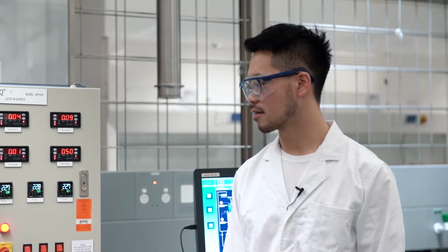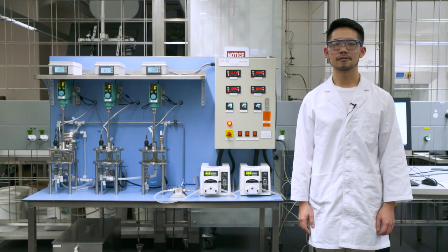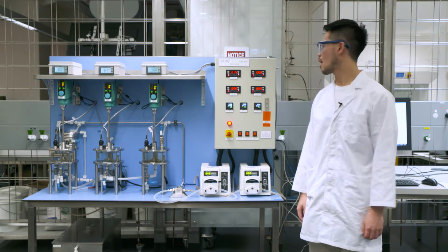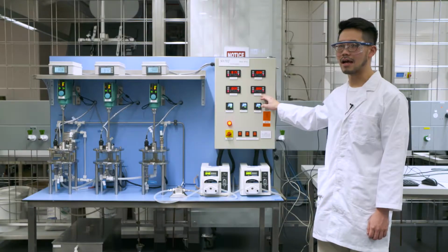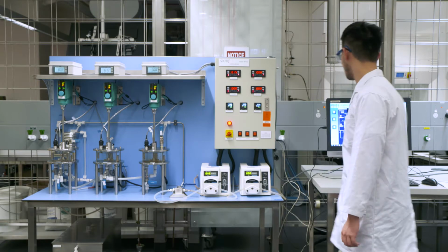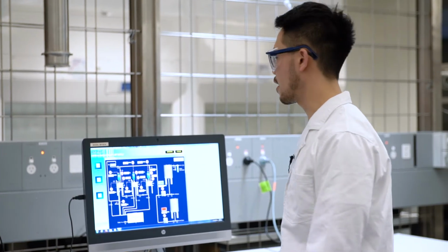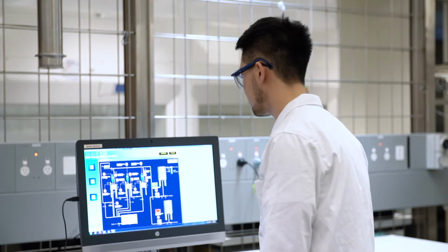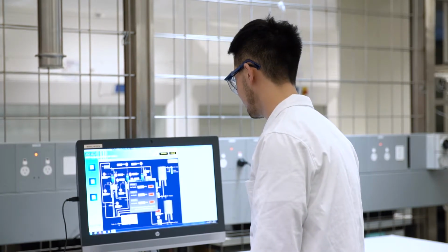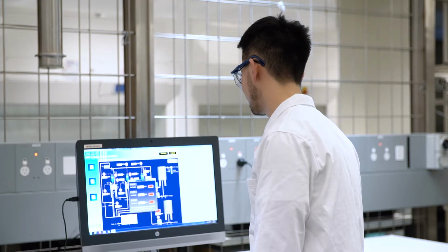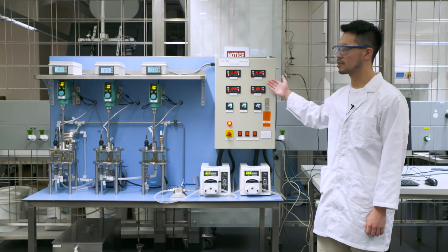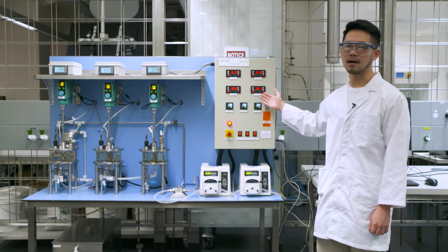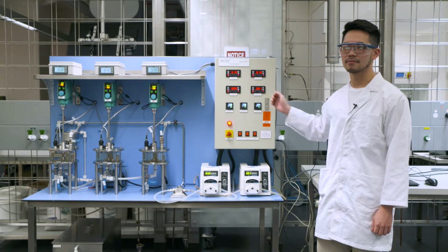After that, we will switch back to pump P1 and let the water go through the system again. We will run pump P1 until the reading of QT04 on the control panel reaches a really low value. After that, we will start the stirrers on the software. The speed of the stirrers is set to 200 RPM. After you start the stirrers, you need to record the values of QT1, QT2, QT3, and QT4. This will become the experimental baseline for your experiment.